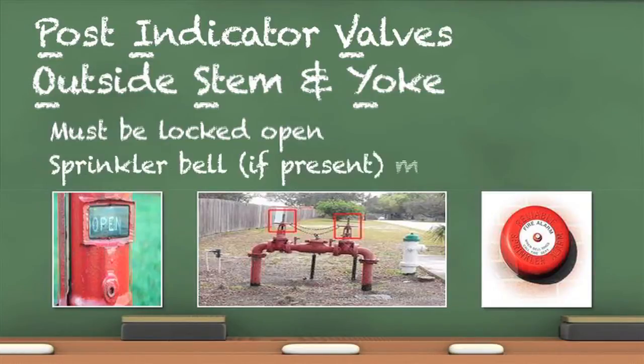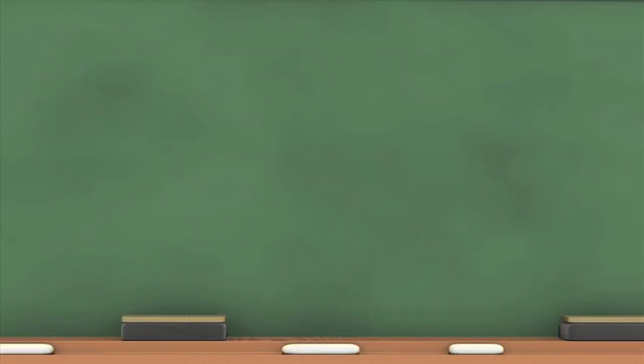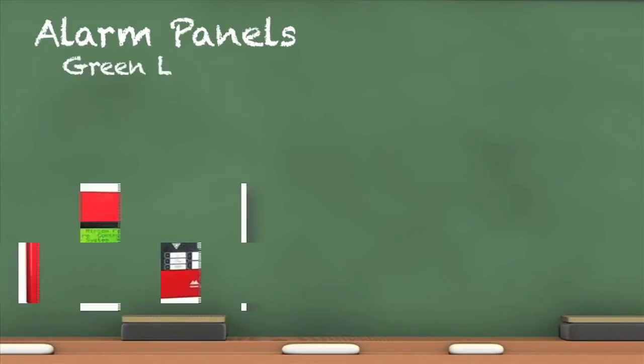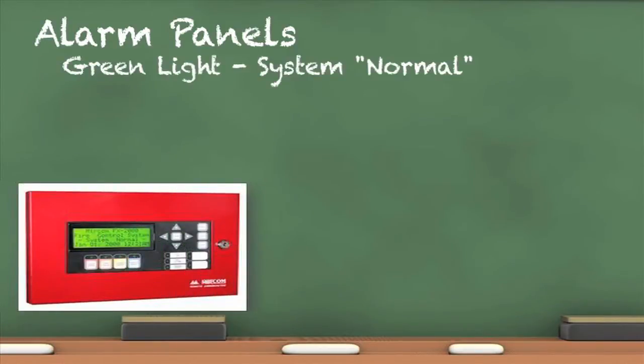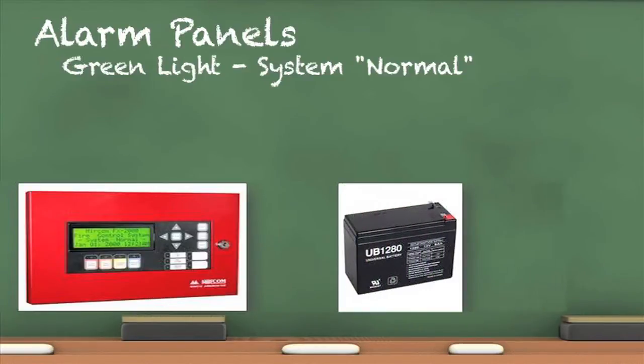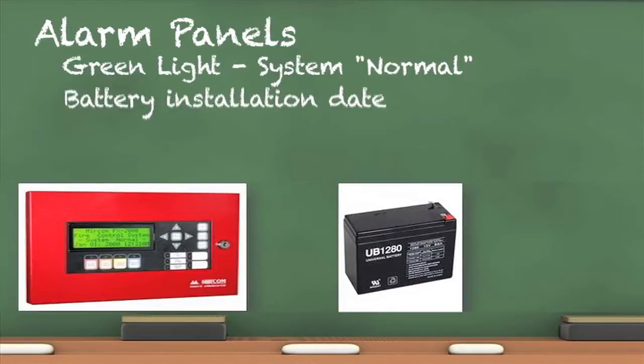Fire alarm and sprinkler bells must be clearly labeled with instructions to call the fire department when the bell rings. On the interior of the building, check the alarm panel. All the lights should indicate the system is functioning normally. Some alarm panels have a display that provides detailed information about the system's status. Alarm panels are required to have backup power. When the backup power is provided by batteries, the installation date must be indicated directly on the battery.